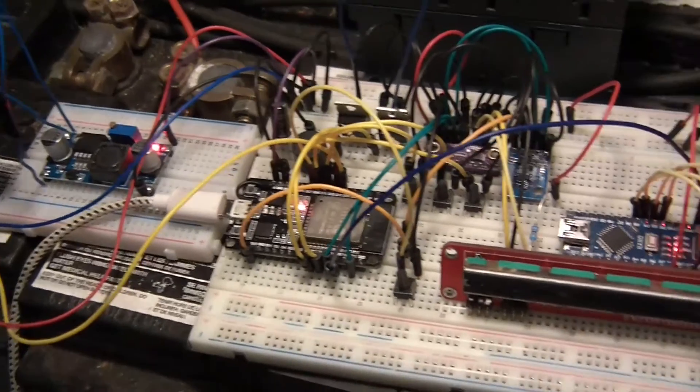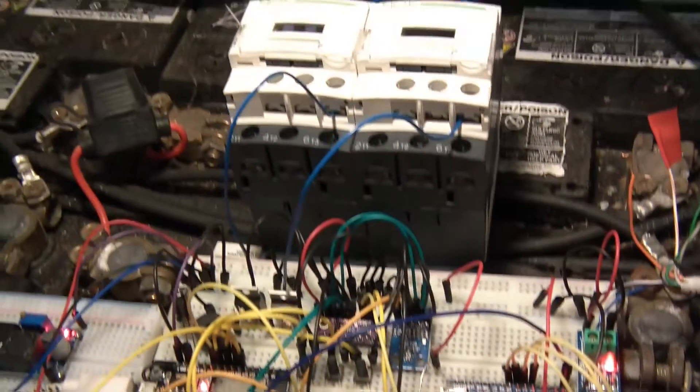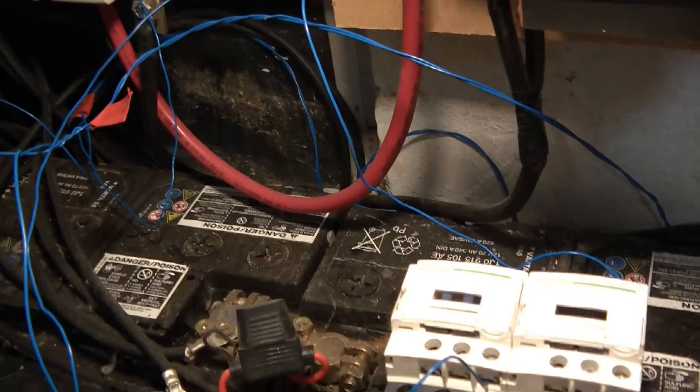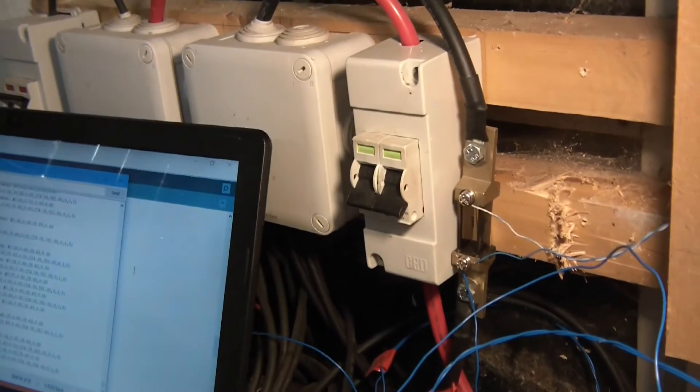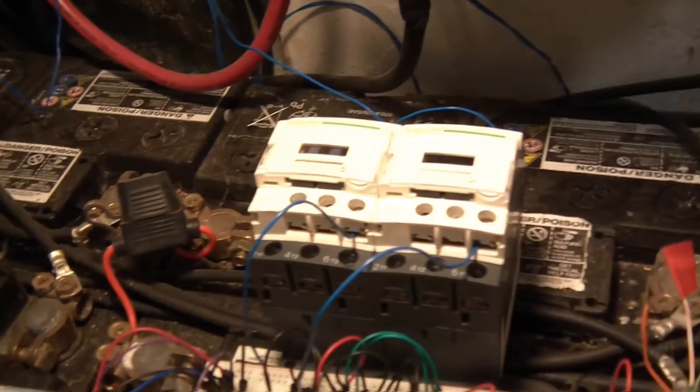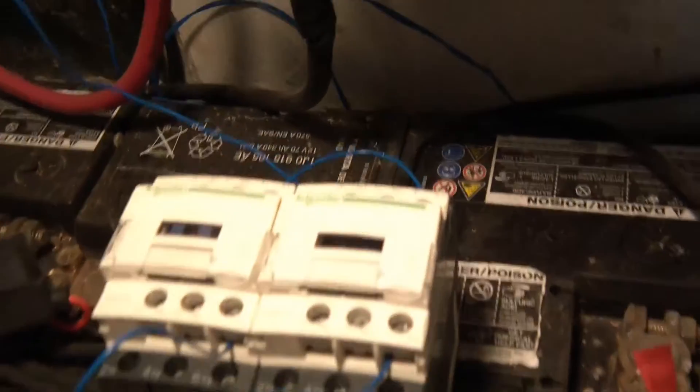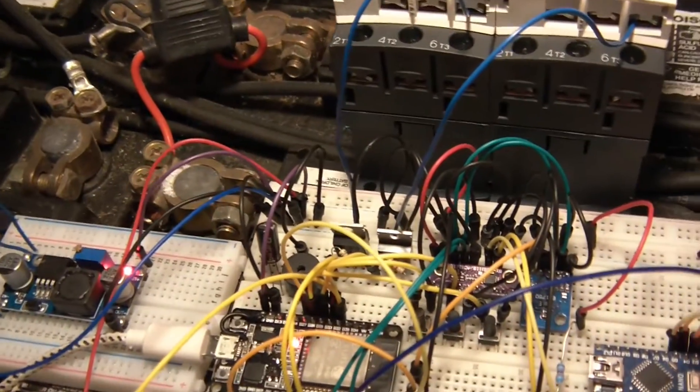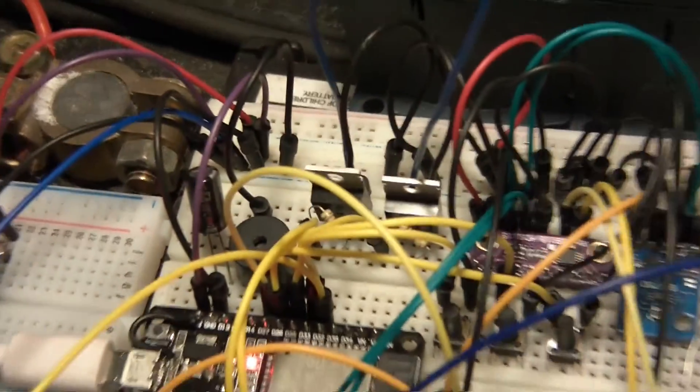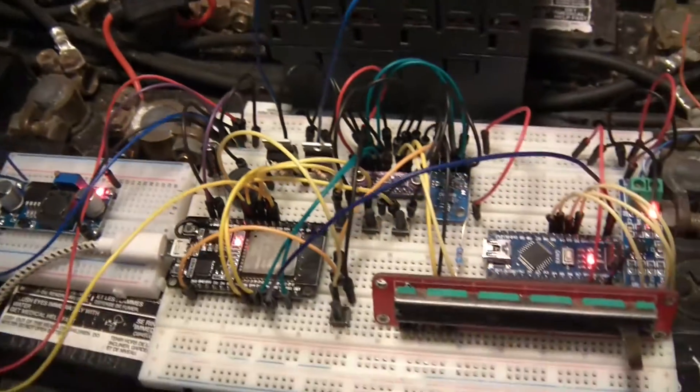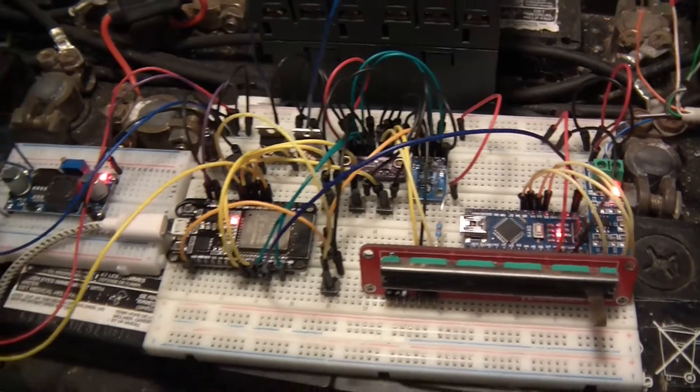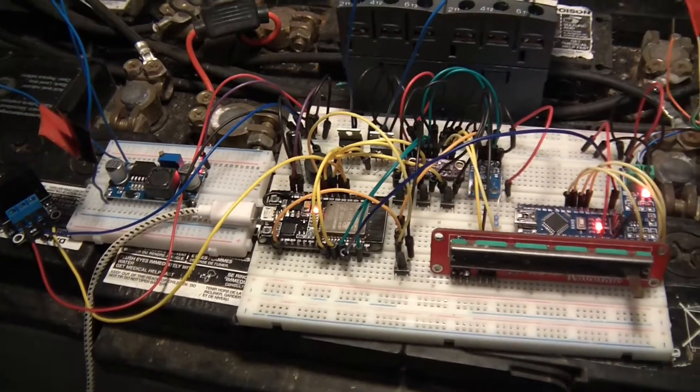And there you go, so that's how it's powered. The contactors, they get 24 volts from the main battery area down here and they're both parallel together. And the switching is done on the low side via these transistors. And as regards to power, that's pretty much all there is to it.